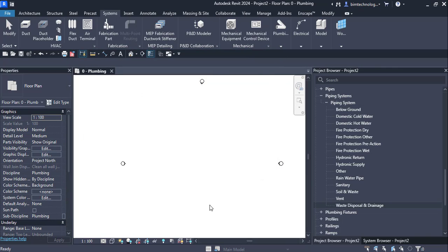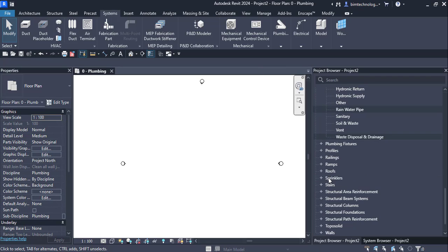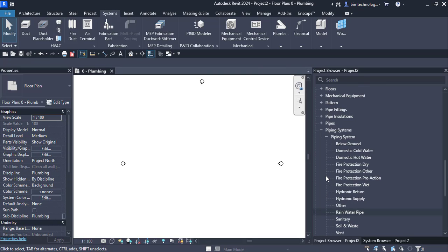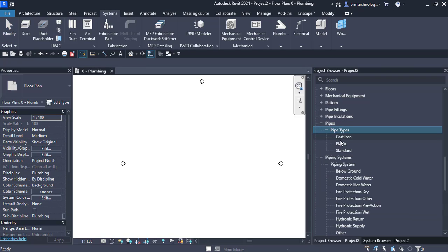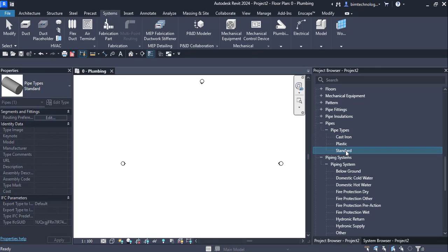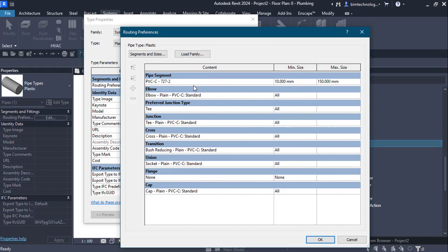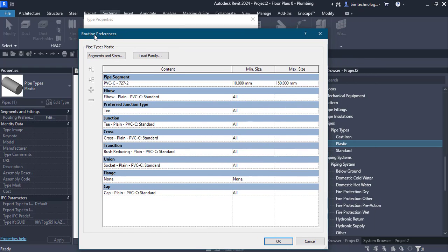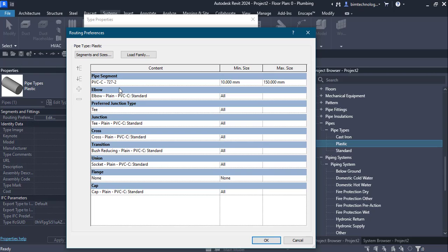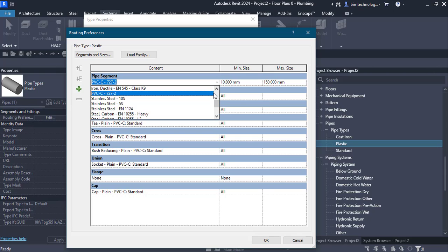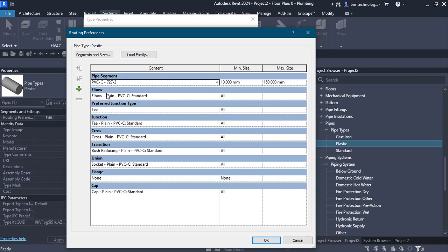Now let us look at how pipes can be created and connected to plumbing fixtures. First, let us see what pipe types are available. In the project browser, go to the pipes option and under pipe types you have a CI pipe (cast iron), a plastic pipe, and a standard pipe. For the plastic pipe, the system family is pipe type and you have routing preferences. Choose the edit button for routing preferences — here you can select the pipe segment from a drop-down; in this case it is PVC-C 727-2, with a minimum size of 10mm and maximum 150mm.